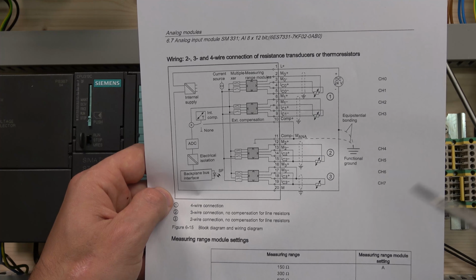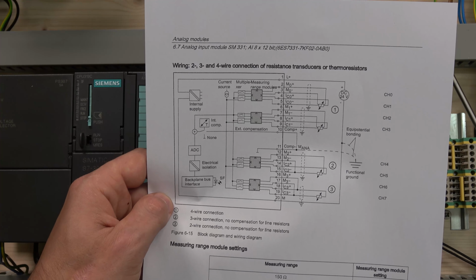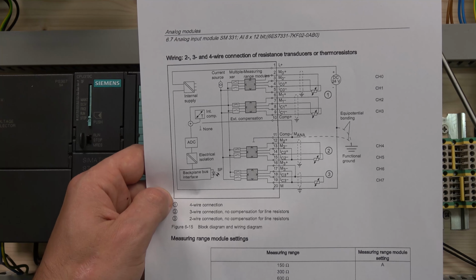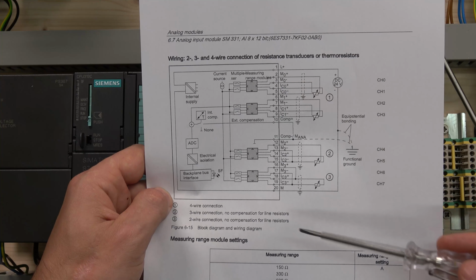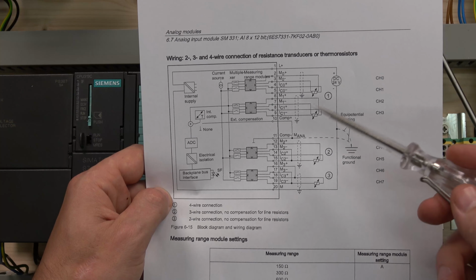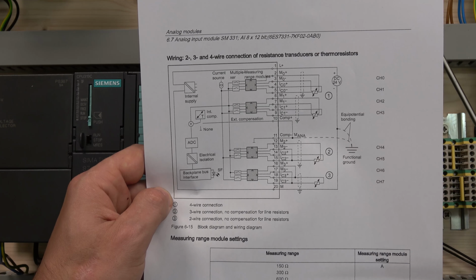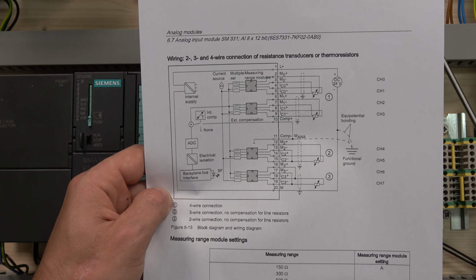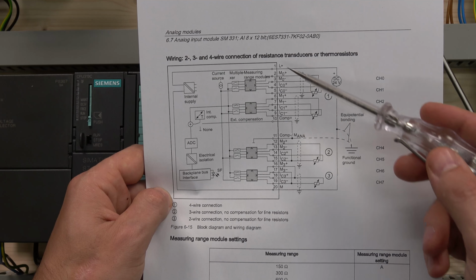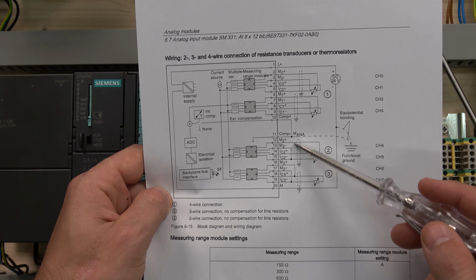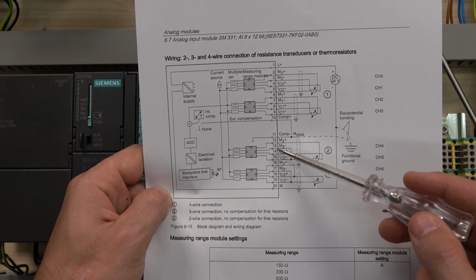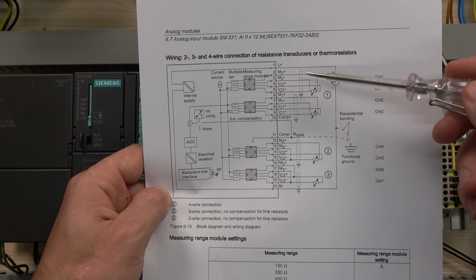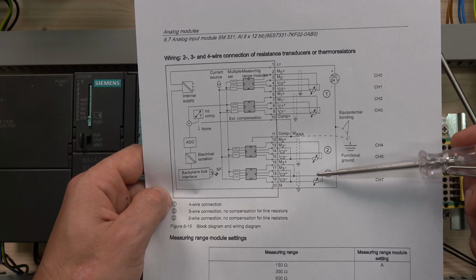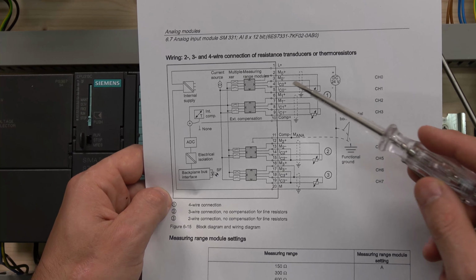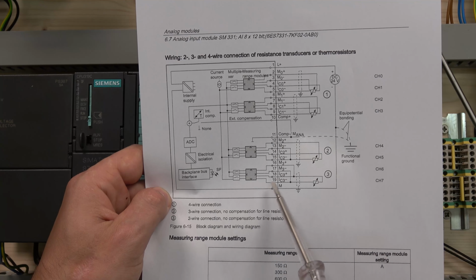As you remember from the previous video, if you have watched it, when we played with the four-wire current transducers, the channels consist of groups of four, and it occupies two channels. So as you can see, you can have four temperature probes connected to your card itself, and each one of those will occupy a group. And as you can see, it shows in here. The way it's displayed doesn't mean these can do this and these can do just that. No, all the channels can do all the things. So we're going to be using the first channel with this wiring, as you can see down here.